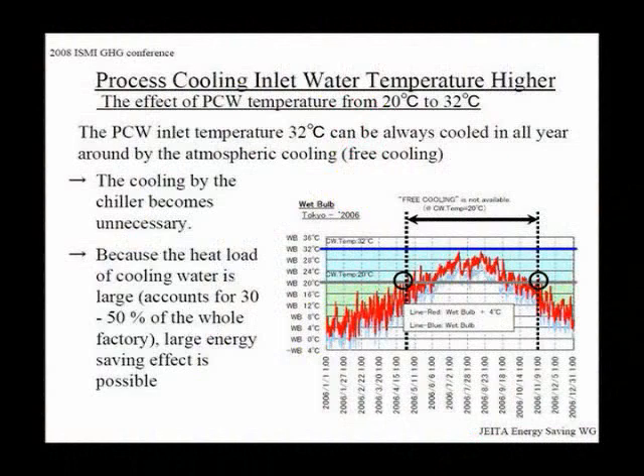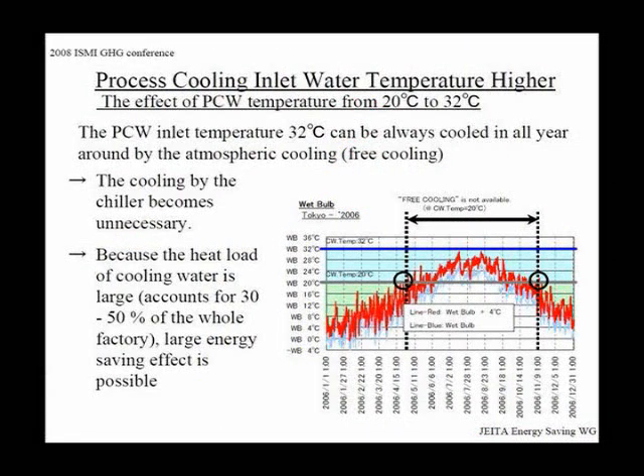And I'm happy to say that this is being considered as a Japanese standard for fabs now. At one of the JEITA meetings, Japan Electronics and Information Technology Industries Association, they took this up. If you look at the 12 months of the year, this is the possible cooling water temperature you can get from certain locations in Japan. And they are going to work with the vacuum pump suppliers and get rid of the requirement for chilled water. So it's kind of a no-brainer.